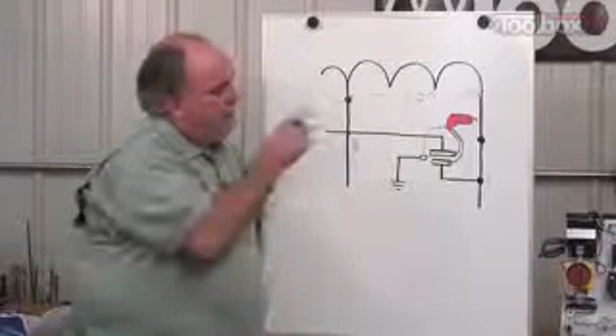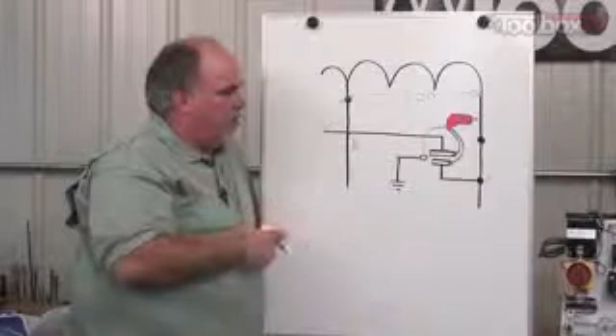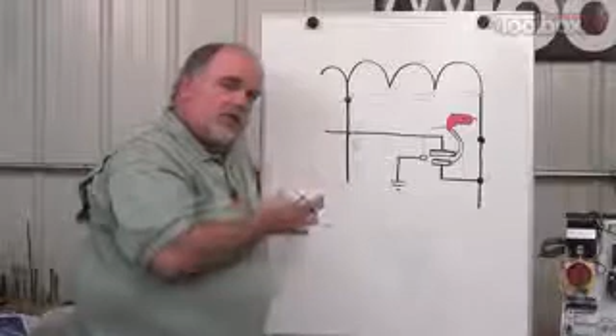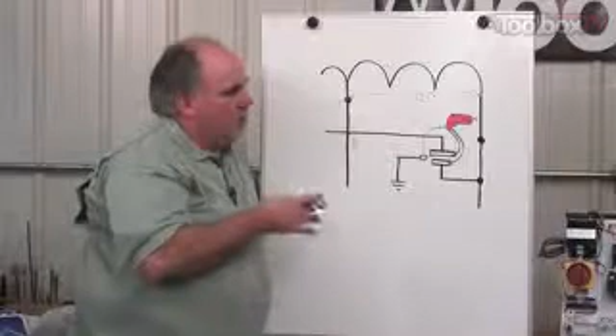If inside that drill, let's say the drill overheats from misuse. You've been drilling a whole bunch of stuff and it overheats, and the insulation on the conductors of the motor winding melts and breaks down. So now the windings, the part connected to the hot wire, have grounded out and are now connected to metal parts of that drill. Maybe the drill's got a metal handle or metal on the case, certainly they have a metal chuck. So the thing's grounded out now.